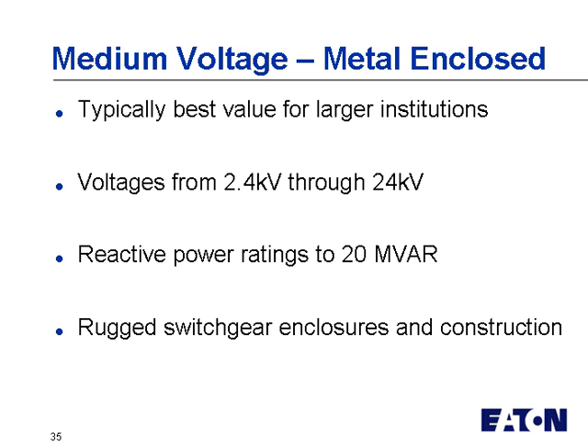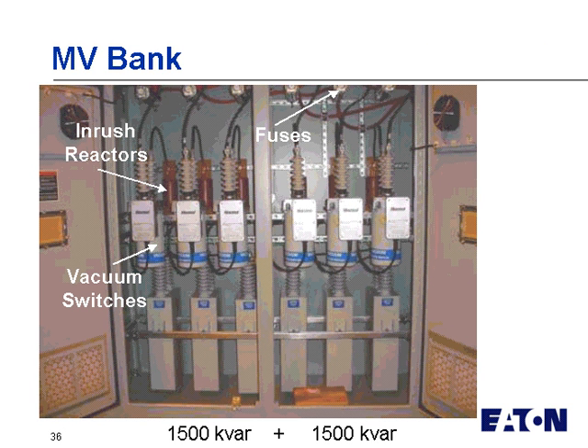Medium voltage are typically the best value, meaning the lowest dollar per kVAR value, and they're in the range of 2.4 to 24, or even sometimes higher kV range. And sometimes you can pack as much as 20 megavar into some of these metal enclosed banks. We could use parallel banks for larger systems, and they're typically rugged switchgear enclosures.